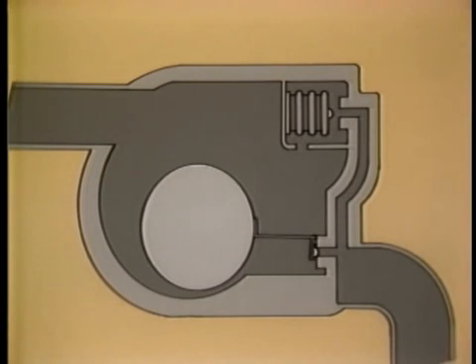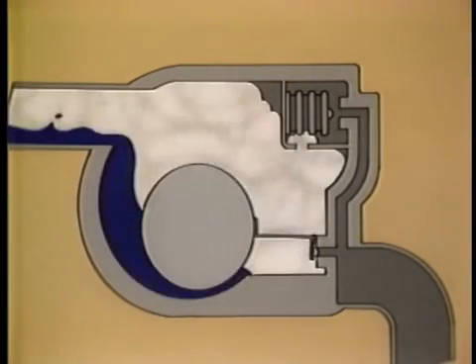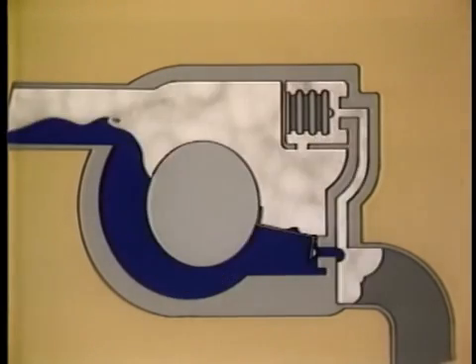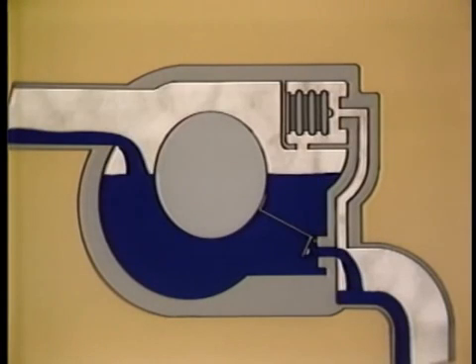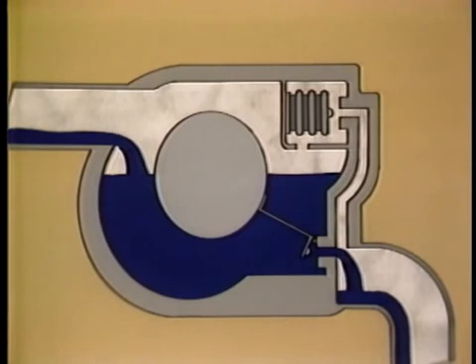Condensate enters through the inlet near the top of the trap and raises the float, opening the valve. The condensate drains from the trap through the outlet near the bottom, leaving a condensate seal between the inlet and the valve.